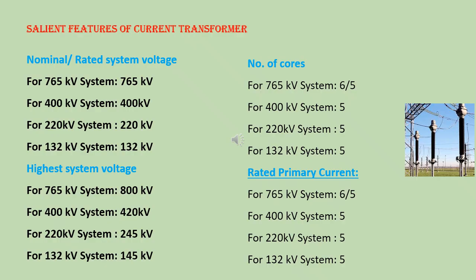In third step, number of cores. There are 6 or 5 cores in 765 kV system, 5 cores in 400 kV system, 5 cores in 220 kV system, 5 cores in 132 kV system. Fourth, rated primary current. For 765 kV system, rated primary current is 6 or 5 ampere. For 400 kV systems, rated primary current is 5 ampere. 220 kV system, rated primary current 5 ampere. 132 kV system is 5 ampere.